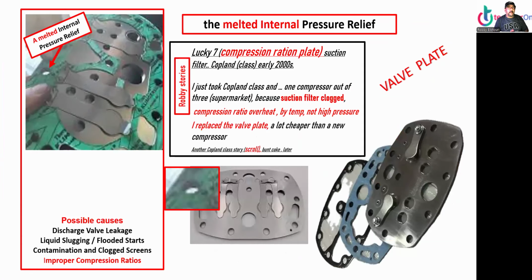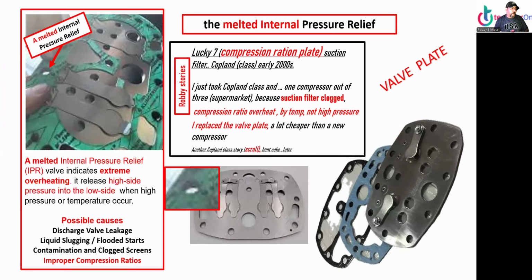All right, now the melted internal pressure relief. So another story that I'll cover in a while. A melted internal pressure relief valve indicates extreme overheating. It releases high pressure into low pressure when high pressure or temperature occurs. Possible causes: discharge valve leaking, liquid slugging, flooded starts, contamination, clogged screen, improper compression ratio, clogged suction line filter.